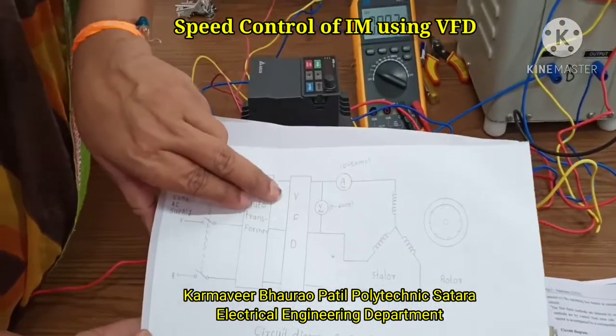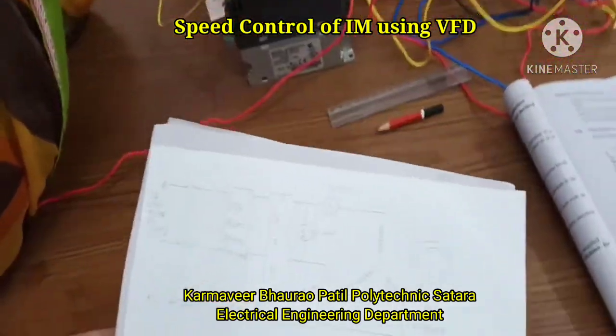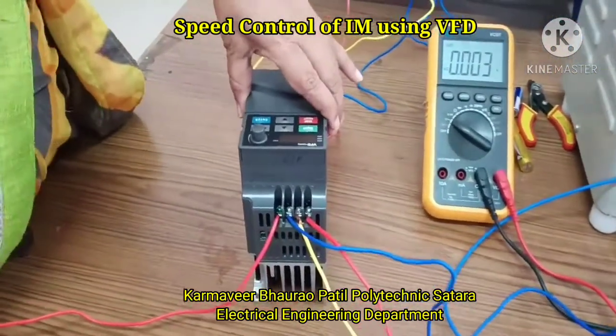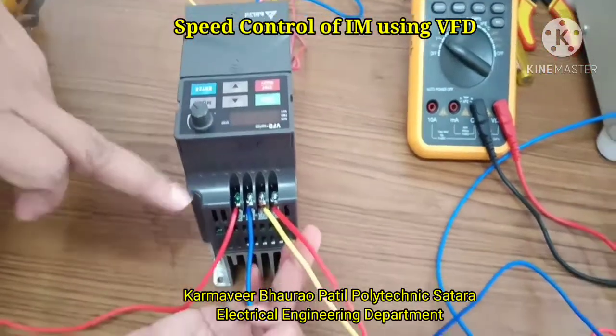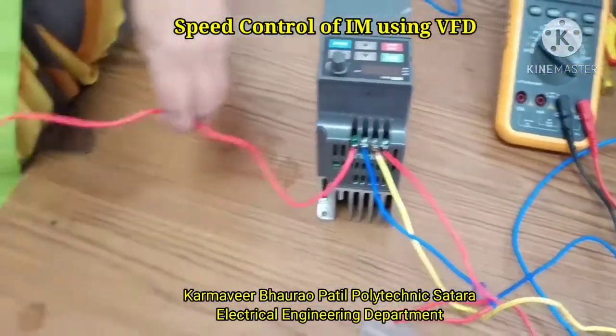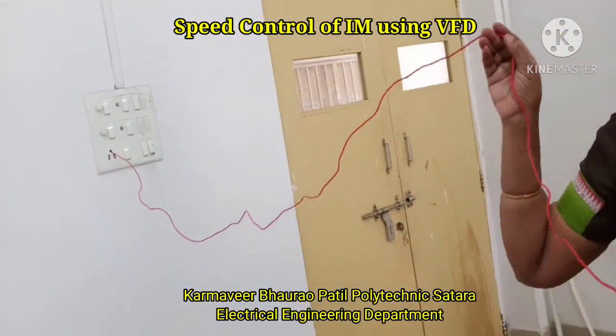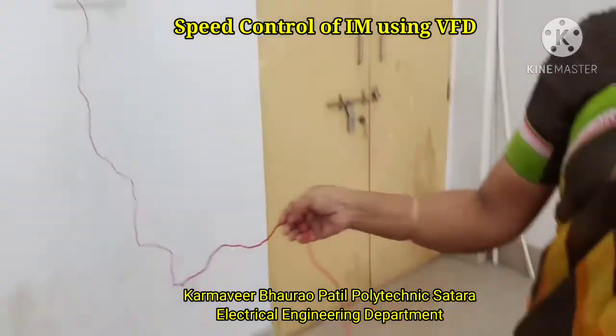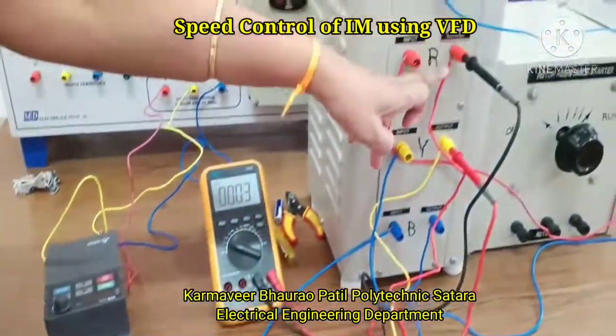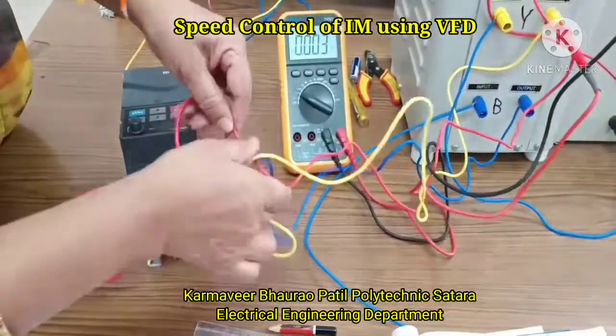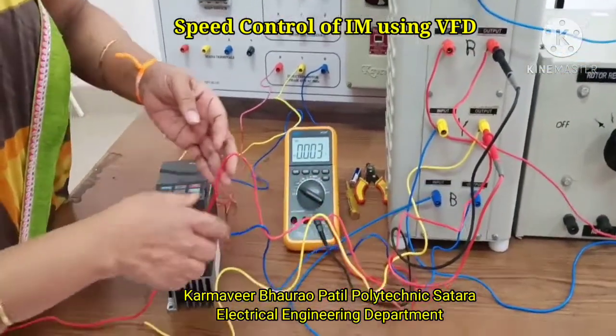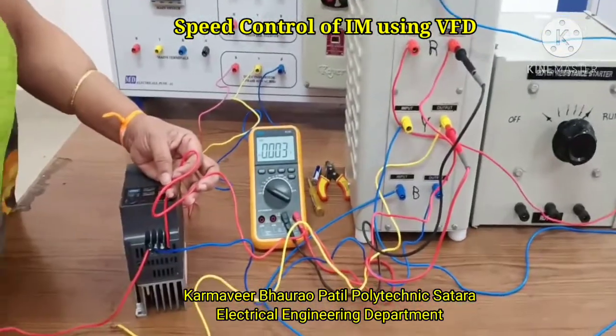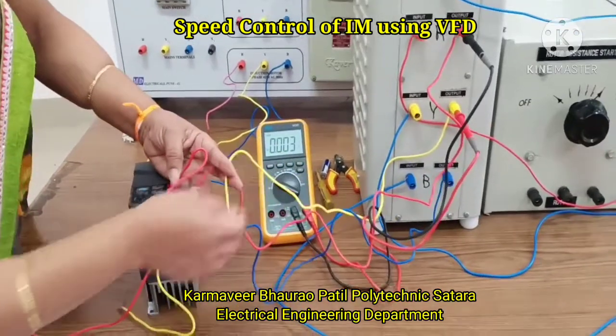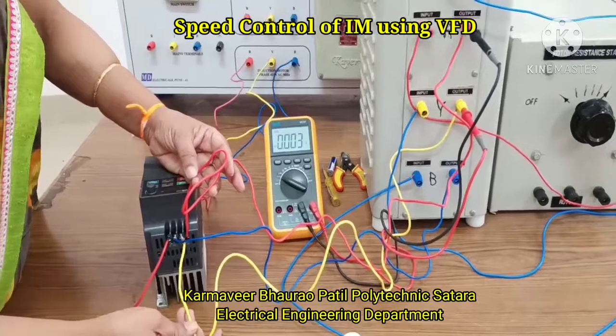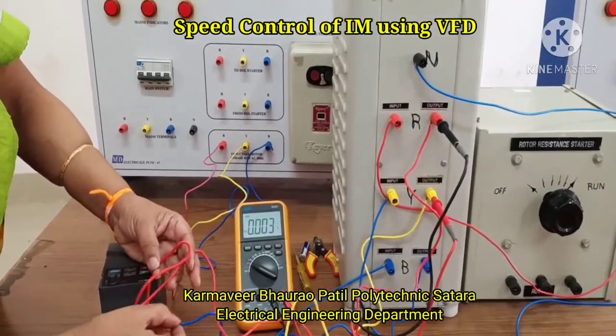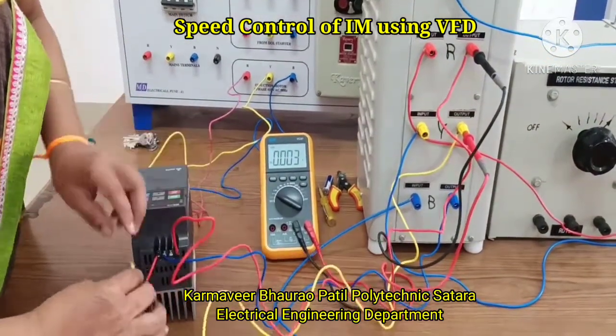RYB of the auto transformer will be connected as input to the VFD. Now you will see here, this is a VFD. You will see 4 lines for the input: R phase, Y phase, B phase and the neutral. Neutral we have connected to the main supply earthing point. Auto transformer output R terminal is connected to the VFD drive's input R terminal. Auto transformer output Y terminal is connected to the VFD input Y terminal, and the auto transformer B phase is connected to the input B phase of the VFD drive.